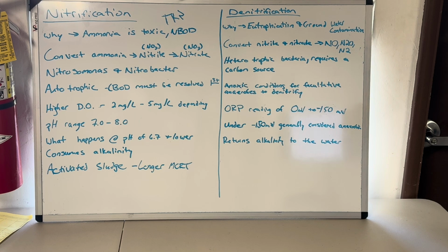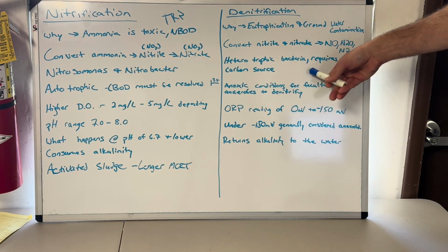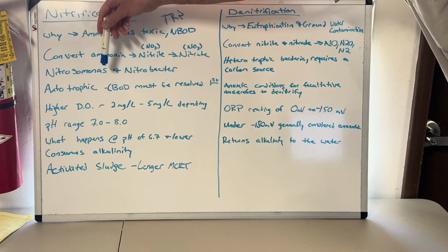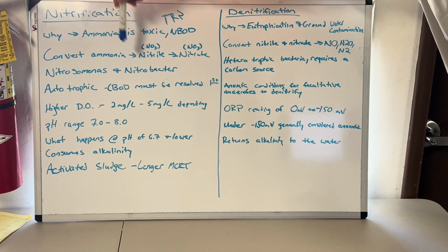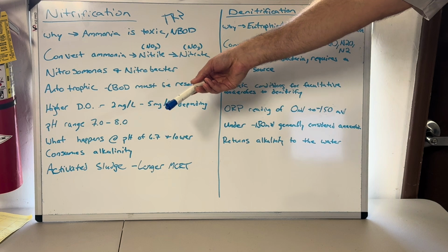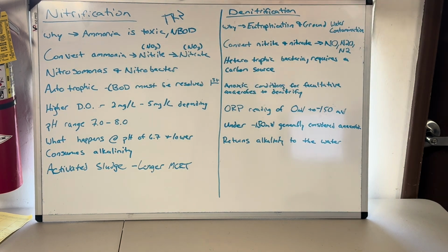And what I have seen the most, I don't know if this is statistically correct, but it is anecdotally correct, is you return your nitrified RAS, return activated sludge, back to the front of the plant where you've got a high BOD concentration, either in an EQ basin or an actual dedicated anoxic selector or an anoxic zone. So I worked at a plant where we returned to the EQ, it worked fine. And I currently work at a plant where we have an anoxic selector and it works great.